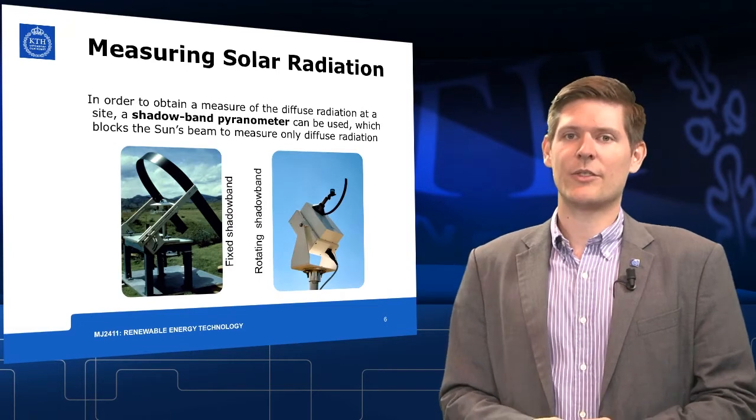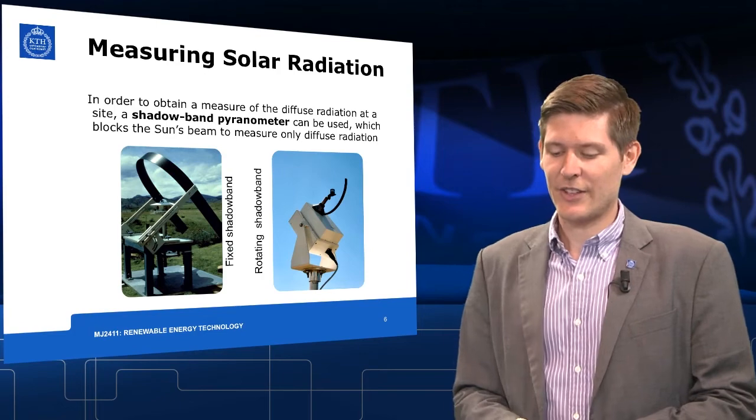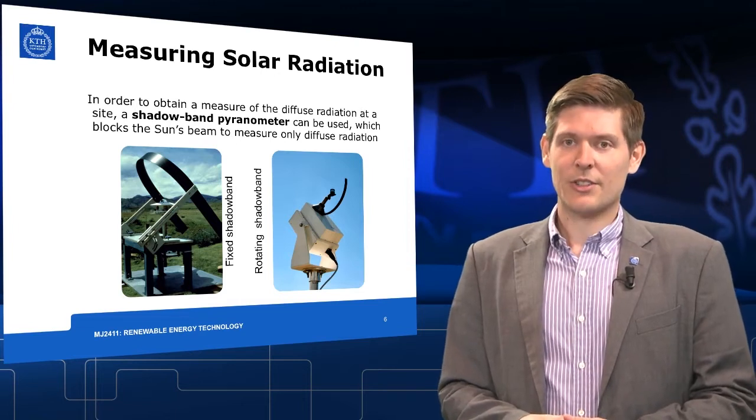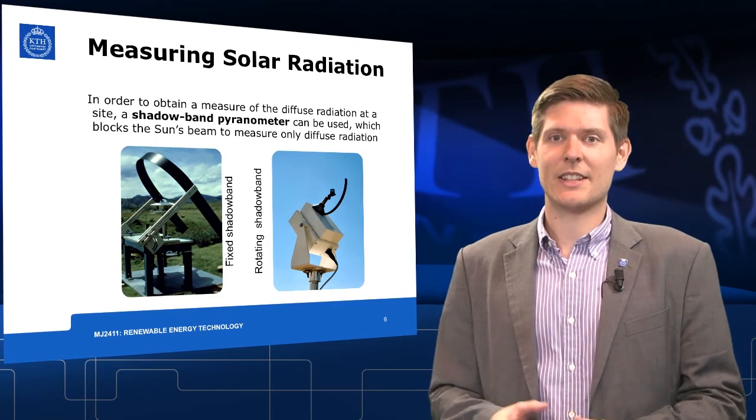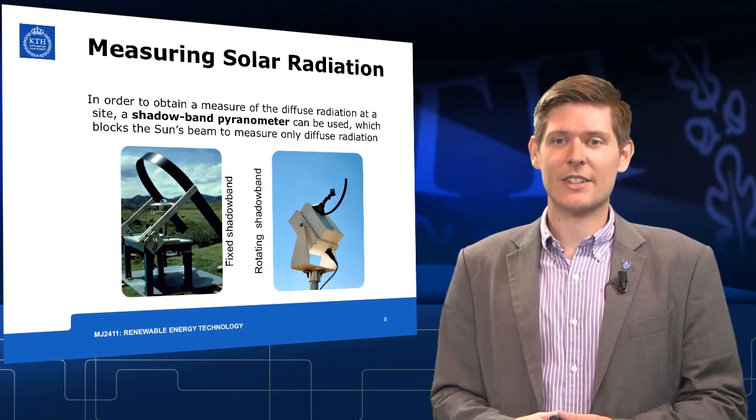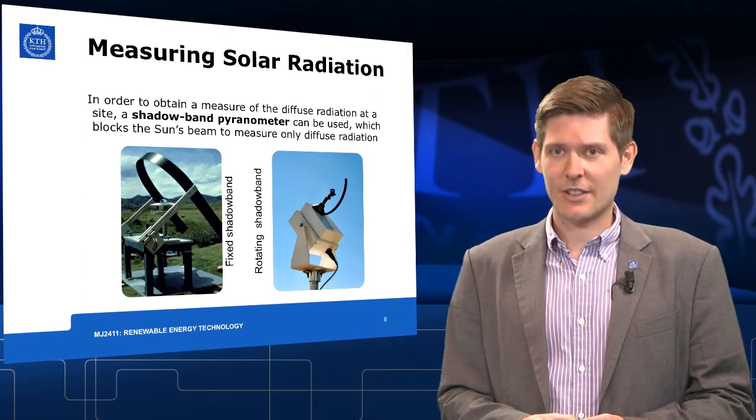There are commonly two different pyranometers with a shadow band used. We have on the left the fixed shadow band pyranometer, and on the right a rotating shadow band pyranometer. In the rotating shadow band pyranometer, the shadow band rotates within a matter of seconds and is able to measure both the total and the diffuse radiation. The fixed shadow band pyranometer is only able to measure the diffuse radiation.